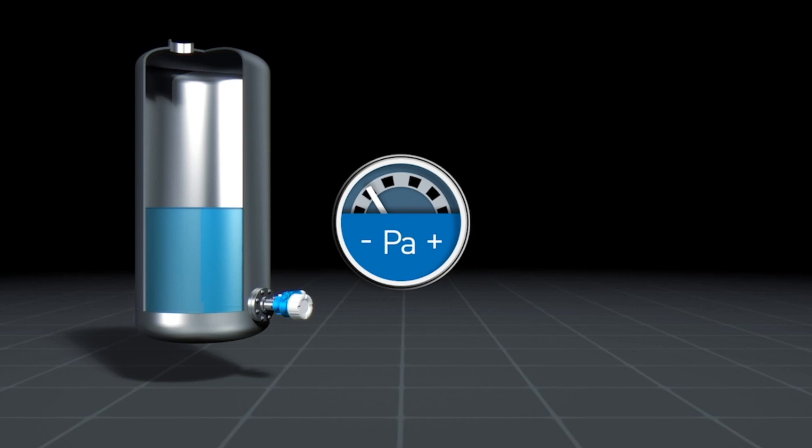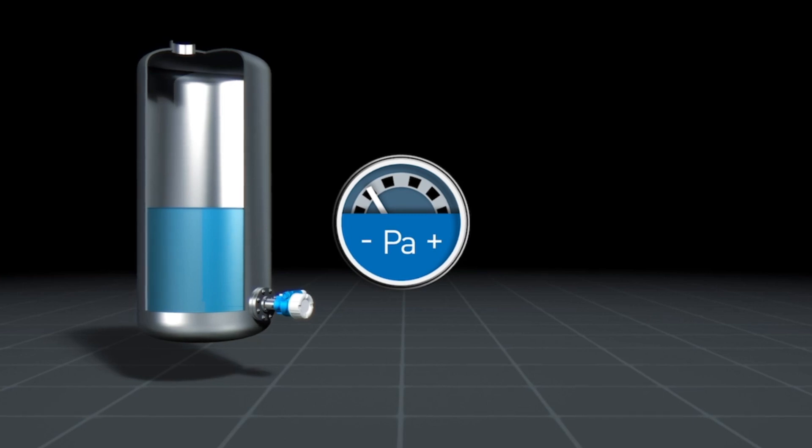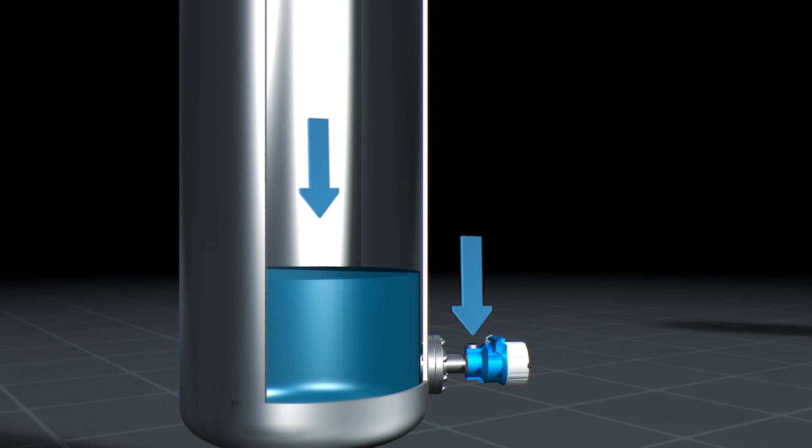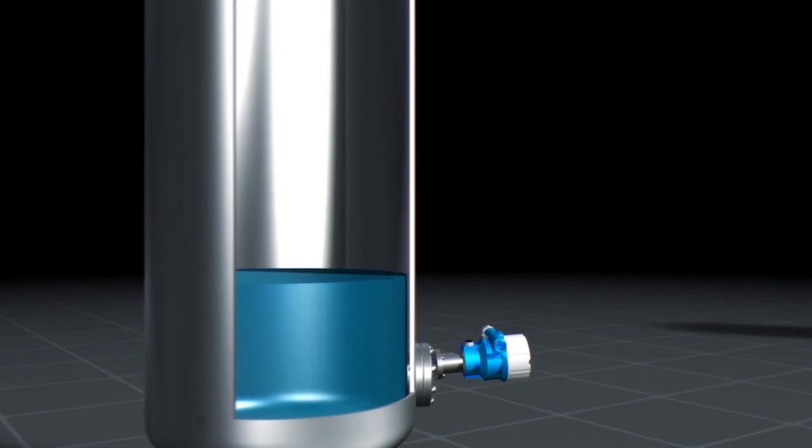In an open tank, pressure is continually compensated in relation to ambient air. Therefore, the gas in the upper area of the tank does not affect level measurement. However, in addition to the pressure of the liquid column, the atmospheric pressure also acts on the sensor. In atmospheric pressure compensation, the sensor is called a gauge pressure sensor. Let's have a closer look at such a sensor.